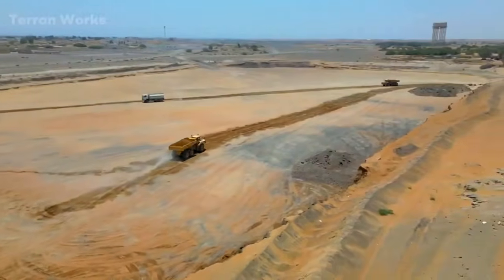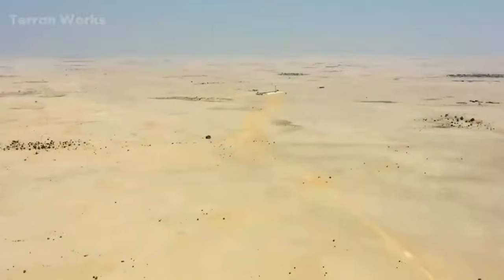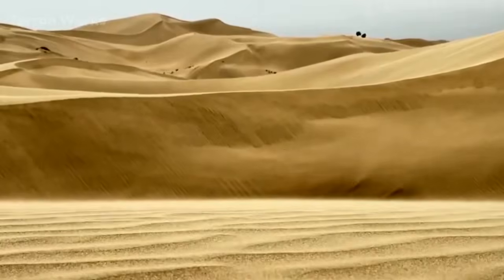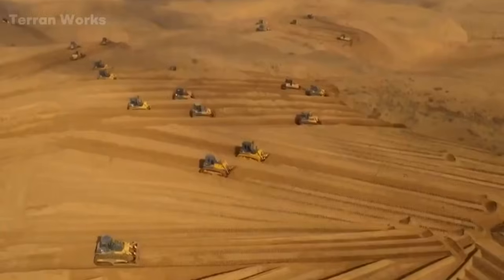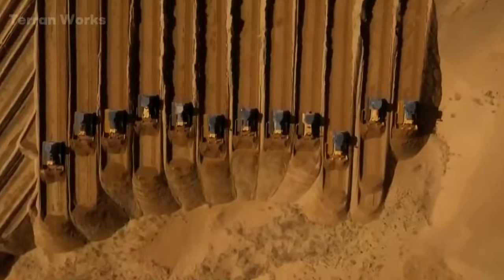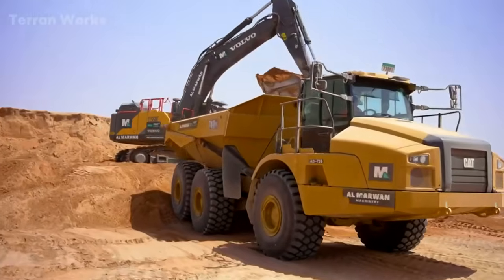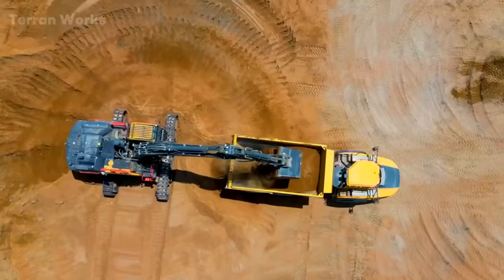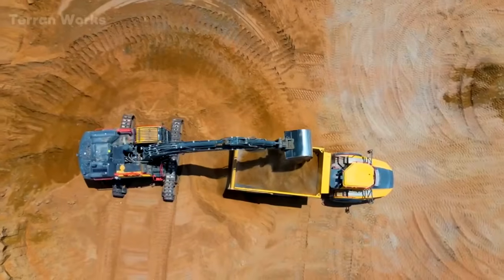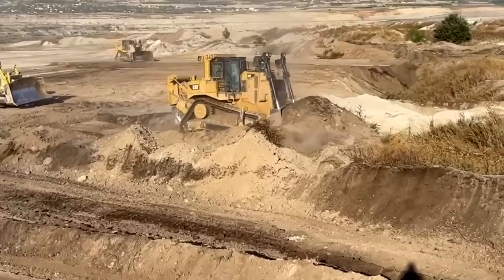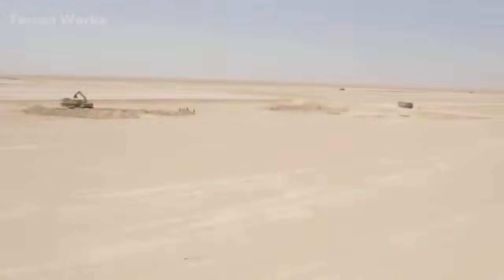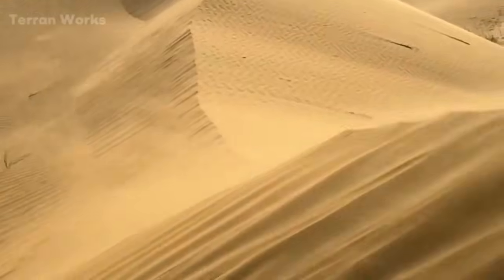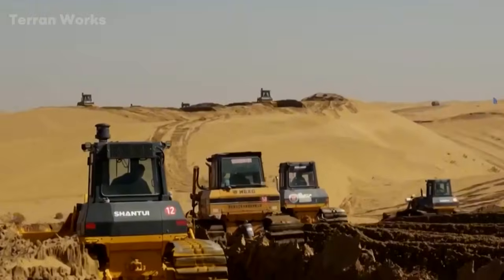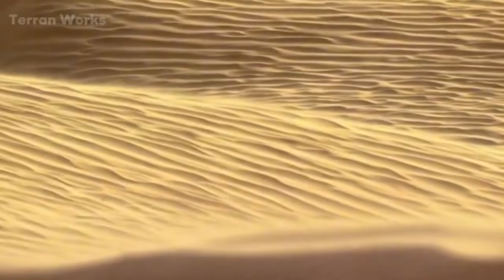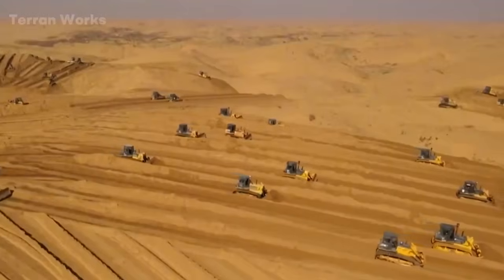Bulldozers and excavators clear shrubs, large stones, and natural obstacles that would interrupt future rows. Then grading machines cut uneven dunes and push sand into low areas, creating a smoother plane for thousands of steel supports. The same leveling preserves the geometry of row corridors and service lanes, so maintenance routes stay inside the design instead of drifting with the ground. That is the hidden risk. If natural waves remain, thousands of support points lose alignment, and panel tables can twist before the array is assembled.